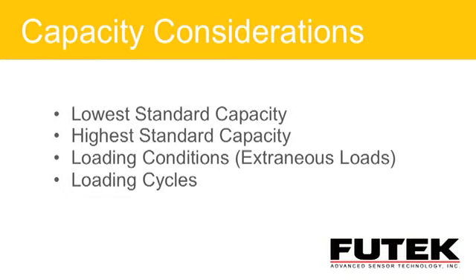Some of the things to pay attention to on your low range and high range is to understand, am I going to have overload conditions? Do I need, as I previously mentioned, do I measure in the 15-pound range? Am I going to possibly spike much higher? I probably want a product that will survive that. Just for your information, standard sensors, and you can look at the data sheets, will have a safe overload range. Normally that's 150%. So if I have a 10-pound sensor, I can only load it to a maximum of 15 pounds. That does not mean that I should continuously load this product to 15 pounds because I want to measure that. It means it will survive that without affecting your specification, but it's not designed to be continuously loaded. If you want to go to 15 pounds, bump up to the next range of 25 pounds, and you should be fine with that.